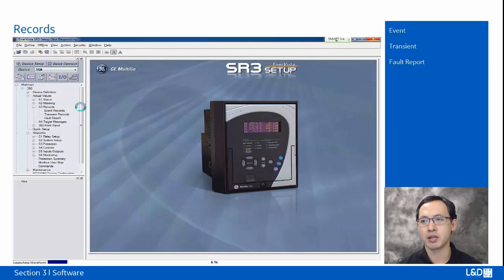This can be preset, triggered by 4 operations: pickup, trip, dropout, alarm. All can be triggered by 3 inputs. These 3 inputs can be configured to be contact inputs, virtual inputs, remote inputs, or logical elements.